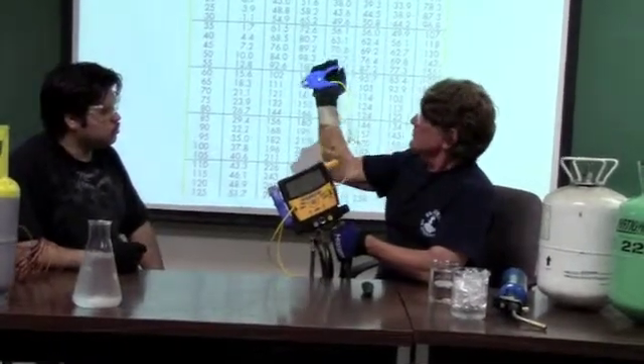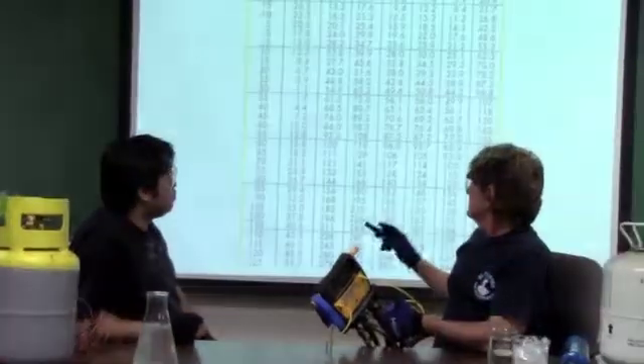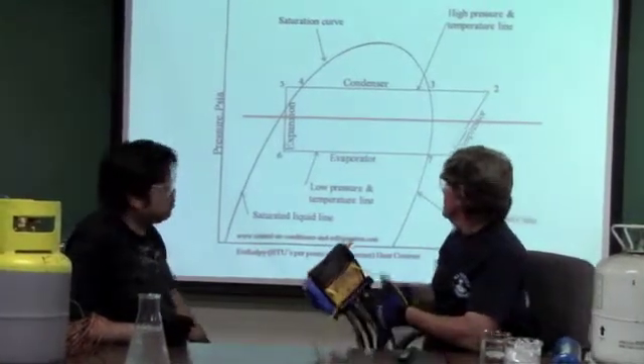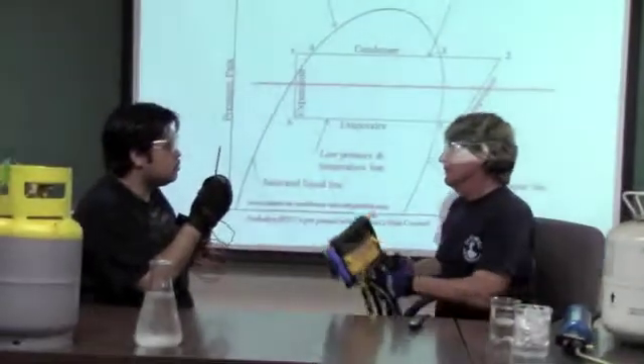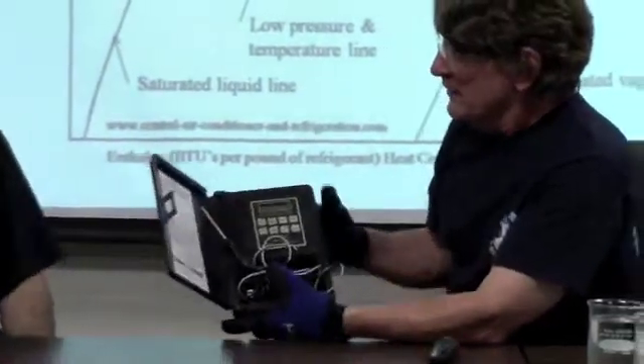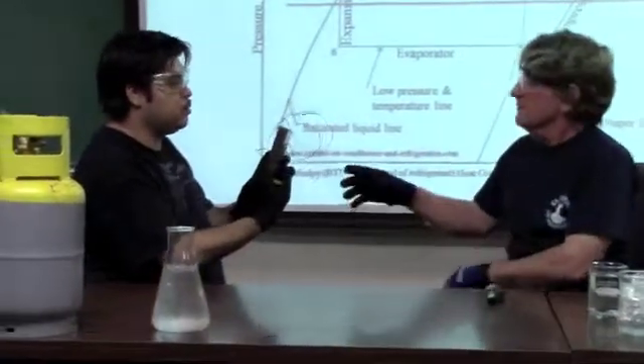So on this one, I've got these little fish-type things that are thermocouples that I can attach to the lines. As it leaves the condenser or evaporator, I will clamp one of these on. What if I don't have one of those? I could use one of these — but is this very practical? Not really, but it would give me a thermometer reading. What about one of these? This is better — I could actually clamp some of these things on to the line; it has some special probes. I could clamp on to the leaving evaporator or leaving condenser. I've got little thermocouples that I clamp on to the leaving condenser and the leaving evaporator, and I can get that second temperature.